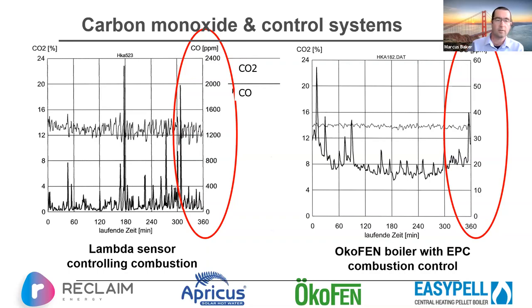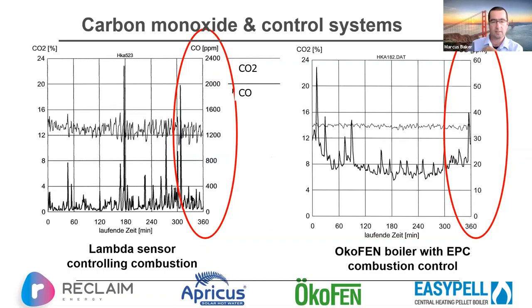With a lambda sensor you're analyzing the gases after combustion — you're always slightly behind because you're sensing the flue gas and looking at what has occurred rather than what is occurring. This can be quite peaky: the carbon monoxide line peaks up to 2,000 or more parts per million, with a baseline of around 100 to 200 ppm. With the Ökofen continuous combustion control, CO peaks at sub-60 ppm, sitting around 20 to 30 parts per million — roughly 10 times less carbon monoxide production.